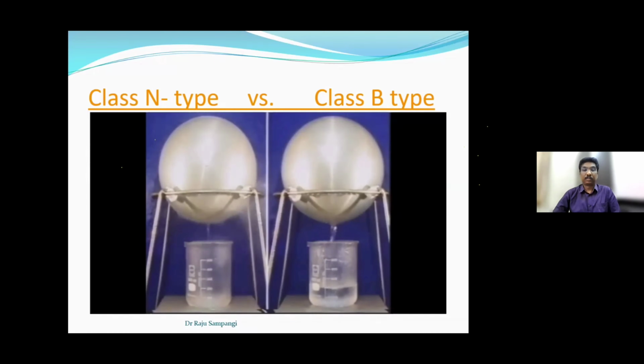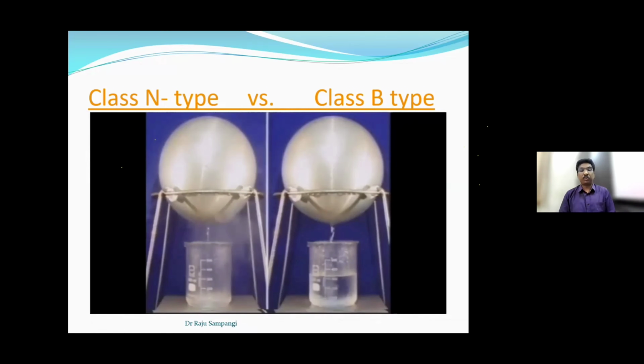On the left side, we see clouds, a mixture of steam and air, and that hinders condensation from taking place. On the right side, we see condensation taking place, and the ball, because of the thermal energy transferred by condensation, is really heated up to sterilization temperature. So, with two balls of similar size, the heat is getting transferred to the ball on the right side, and that's why more heat is transferred and more water is formed at the bottom of the beaker. So in a Class B autoclave, because of the removal of the air, the steam penetration will be better. That's what this video demonstrates.